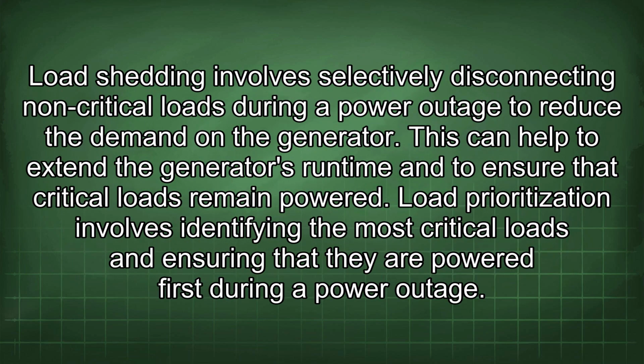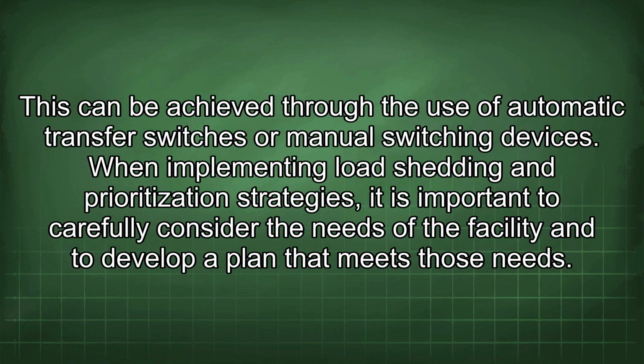Load shedding involves selectively disconnecting non-critical loads during a power outage to reduce the demand on the generator. This can help to extend the generator's runtime and to ensure that critical loads remain powered. Load prioritization involves identifying the most critical loads and ensuring that they are powered first during a power outage. This can be achieved through the use of automatic transfer switches or manual switching devices.